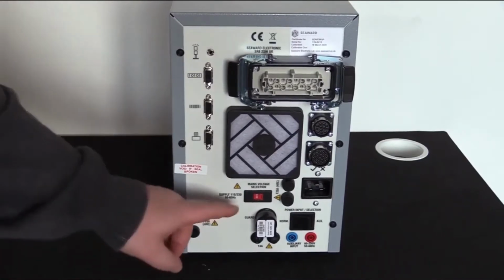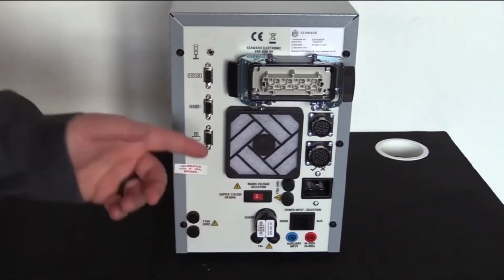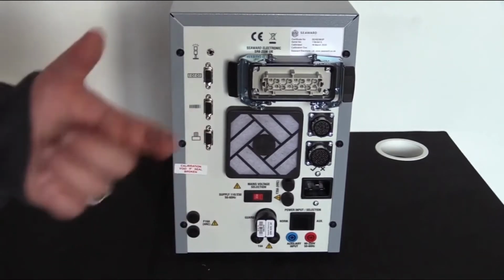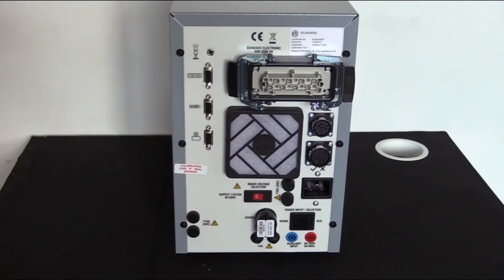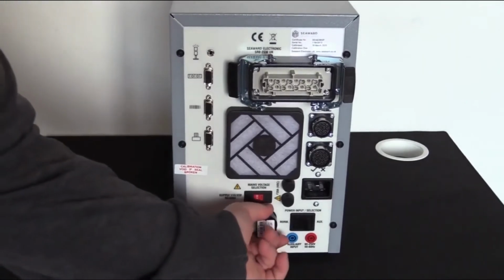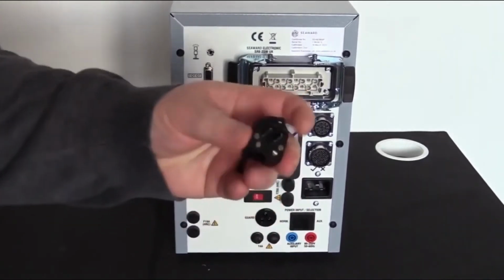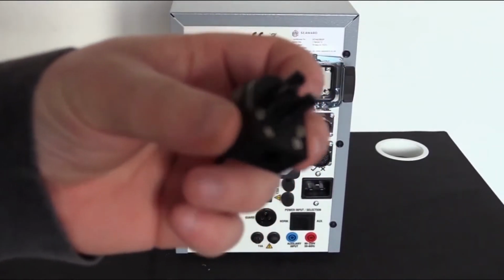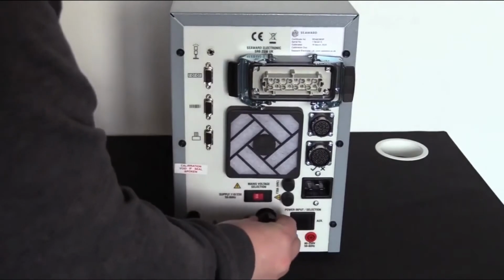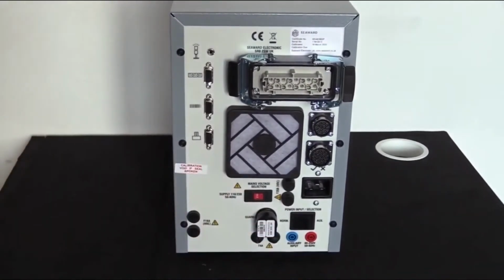We also have on all models a voltage selector switch. So this allows you to switch the incoming mains voltage, whether you're running from a 230 or a 110 volt supply. We also have our guard plug. So our guard plug is a safety connection switch that allows us to stop the test if for any reason the safety switch is broken. So this is commonly used in things like enclosures. When someone opens the lid of the enclosure, the HAL can be programmed to instantly stop the test, providing the enclosure switch is connected to our guard switch feature.